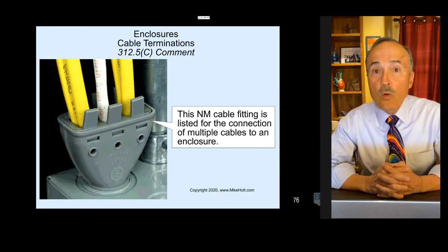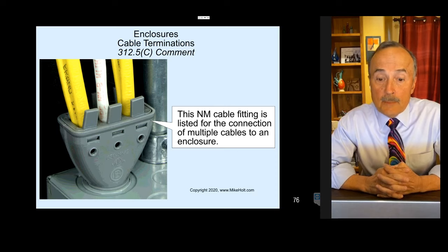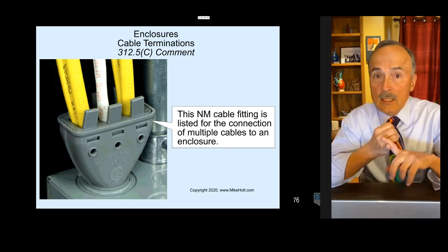Yesterday there was a question about, Mike, can you use like a 2-inch cable clamp and run all kinds of Romex conductors through that? I'm like, no. So let's review it one more time. The basic rule of 312.5(C) says cables must be secured to the cabinet with fittings designed and listed for the cable.